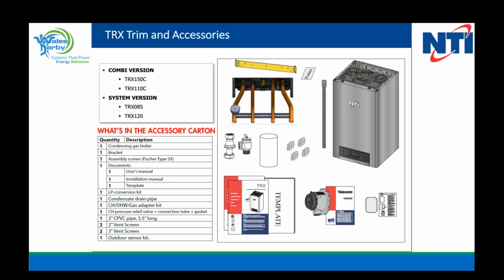This must be installed on the exhaust side of this boiler. We have to have that 5.5 inches of pipe right there in CPVC, because we can have our highest temperatures right at that point. And we have to have straight pipe. We cannot come off the top of the boiler immediately with an elbow. That's no good. That's going to cause us issues. So that comes with the boiler, must be installed. You'll get 2-inch vent screens and 3-inch vent screens, and you will get the outdoor sensor kit.